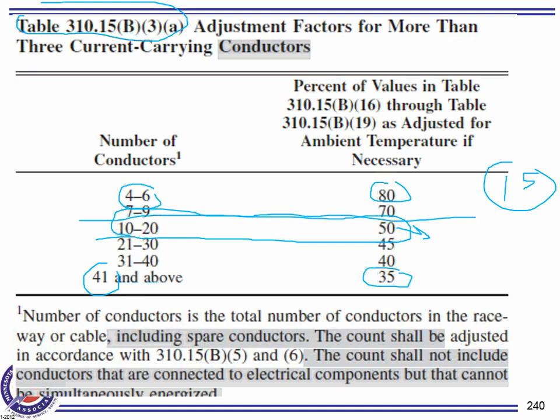But really getting into higher than 50 becomes not cost effective. Okay, now what counts? What counts, including spares? If they tell you there is a spare in the conduit for future use, count it. So on the test, if they tell you there is a spare that's going to be used for a hot conductor or even neutral conductor, you can use it. The count shall not include conductors that are connected to electrical element but cannot be simultaneously energized.